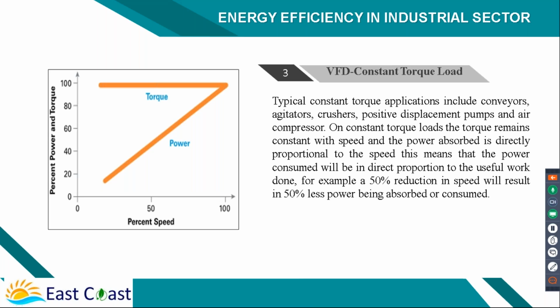Now VFDs can also apply to other constant load applications, for example crushers and conveyors. The dead weight is so much that whether you put 100 tons or 50 tons on a conveyor or crusher, even if full capacity is 100 tons, it doesn't matter. You still consume the same power at that particular speed.